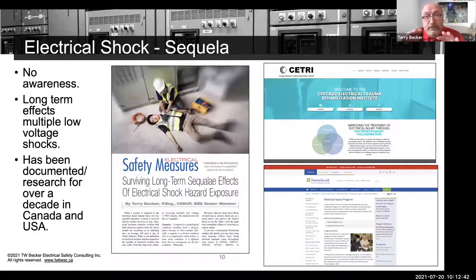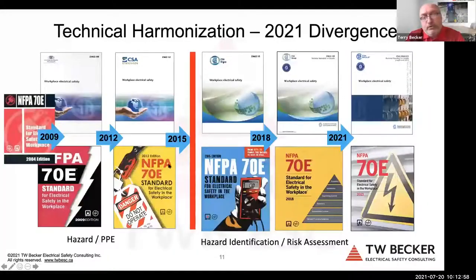So just a brief note, you need to look into this. Go on to LinkedIn. I've got multiple posts. I've got an article on my website as well. I've got a second article that just published, part 2 on this topic of sequelae. So FYI, we need to talk about shock actually more than we're talking about arc flash. And that's another shift, and it's a long-time shift. I've been educating around 2 hazards, and the electric shock hazard actually needs a higher priority than the arc flash hazard. But arc flash has overwhelmed industry, right? There's lots of myths and misinformation. Again, that would be another webinar that I can highlight as well.